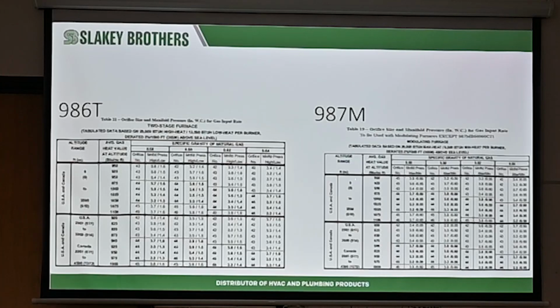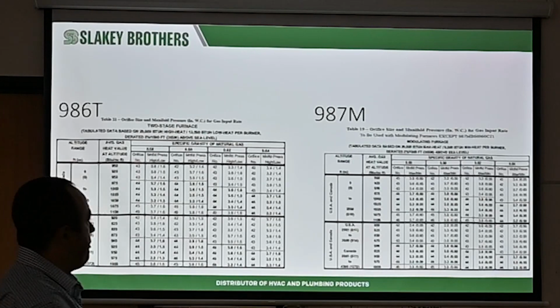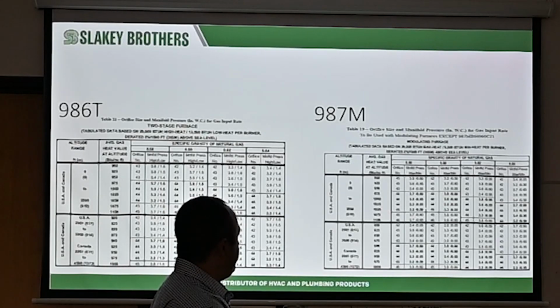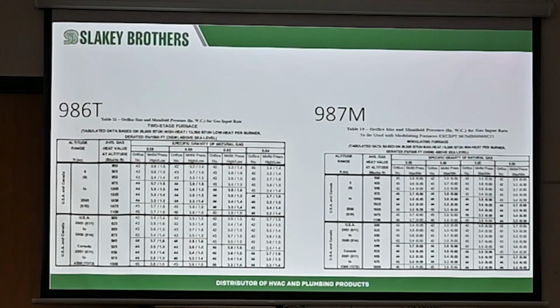When you see this chart, let me just change subjects for just a second. Specific gravity and natural gas and average gas heat value at altitude. Everybody uses PG&E. I've contacted PG&E many times to try to get clarification on their zones so I can know these precise numbers. I couldn't get any real help. In our area, around this kind of altitude and everything, you're going to be safe if you use 0.6 and 1025 or 1050. As you can see, look at your 1025, 3.5, 1050, 3.3. So if you set the high at 3.5 and you do a temperature split and it's a little bit too big of a temperature split, you can just turn it down to 3.3. All that's meaning is maybe in that area the gas has a little more BTU value to it.